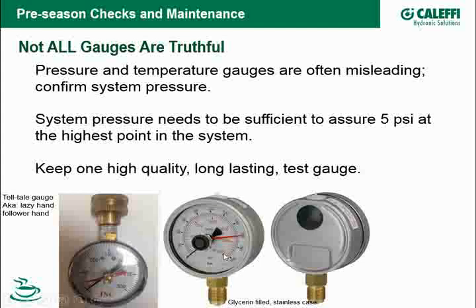So what that does for you is, number one, if you're reading something like a pump output, and it's got a little bit of vibration or bounce to it, the needle won't be bouncing around in there because the fluid kind of dampens it. And the other thing it does, it keeps the needle safe in there. So if this is bouncing around in your truck or your toolbox, you'll see a lot of the inexpensive gauges, sometimes you go to use them, and the needle is falling right off the stem on the end because it can't handle that harsh abuse. So this one looks like it has a little snubber on the bottom of it also, and it's not super expensive. I would say a gauge like this is probably about $30 compared to a $10 or $15 gauge.